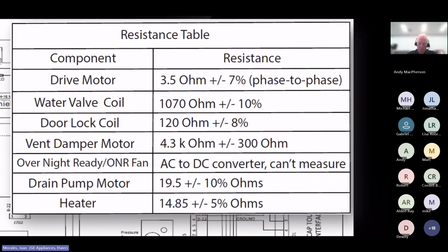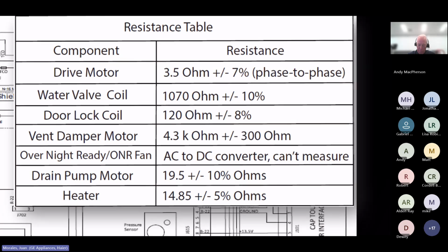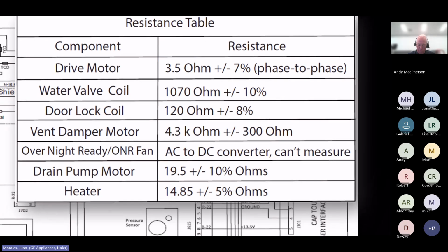So it's telling you that your drive motor phase-to-phase coil resistance is about 3.5 ohms. If we look at the drain pump more toward the bottom, it's 19.5 ohms.